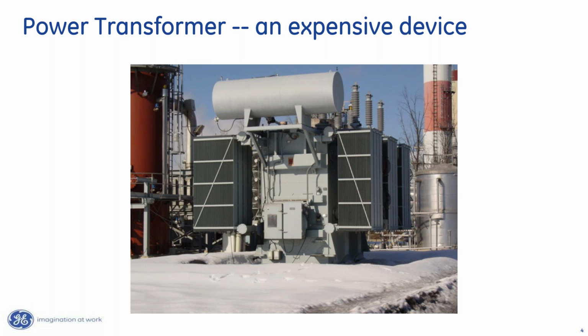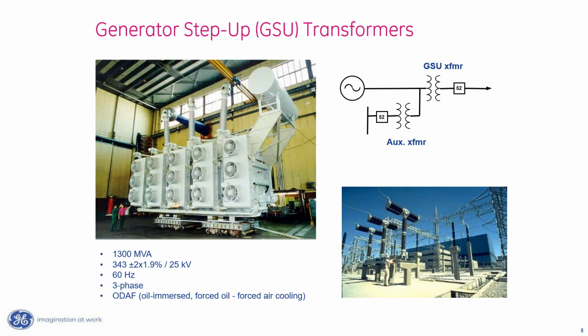And they were expensive. So we want to protect them, and things that we protect that are expensive, we really want to trip fast and limit the damage on, and so that's why we use transformer differential. Now, I broadly categorize power transformers into 3 broad categories, and really I should say 4 broad categories. There's generator step-up transformers, like the one you see here. The generator step-up transformer has 2 real jobs. Its first job is to transform the voltage that we generate from around 13 kV up to a high voltage transmission level so that we can transmit the power at a lower current.